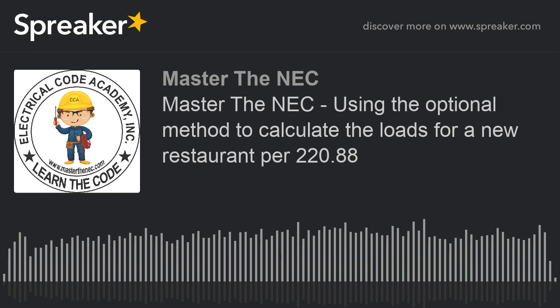And if it's an all-electric restaurant, then you do just like we did: determine the amount that is over whatever's in the parentheses. In our case it was 450, so it says the amount over 325, and it was 125 that is over 325. That's the difference between 450 minus 325, so we can find out what that specific amount is that's over 325. Then you take that value at 50%, and then you add the 172.5 onto it. Okay? Makes sense? All right, so that's how you work it, and that's how you do a new restaurant under 220.88, and hopefully that's been pretty simple for you.